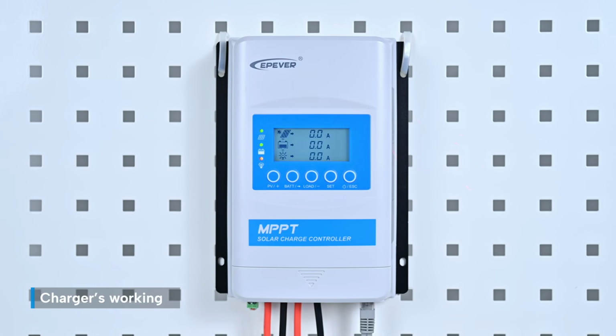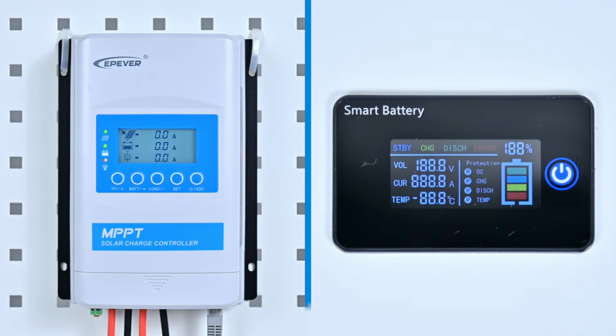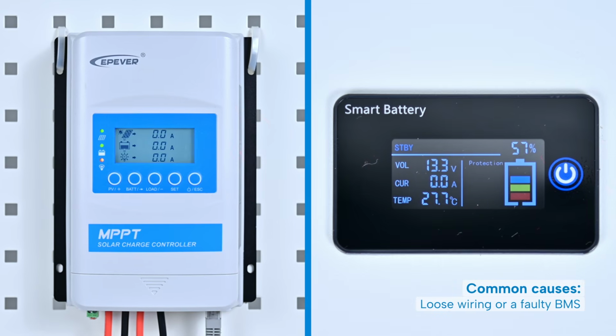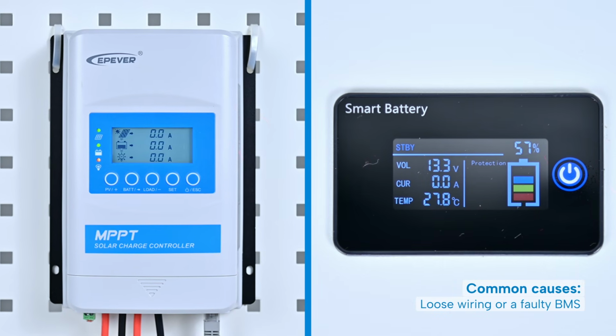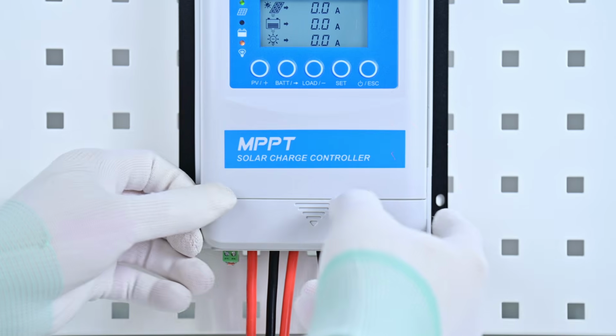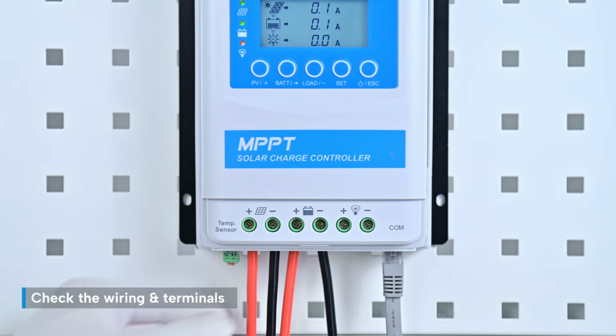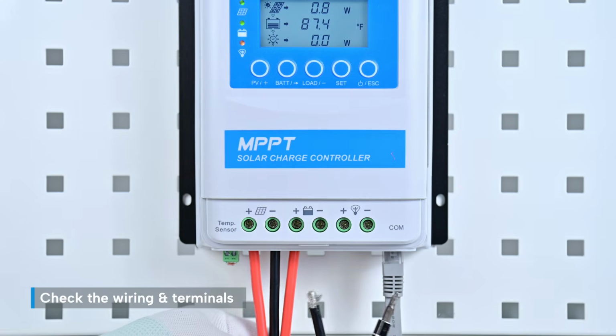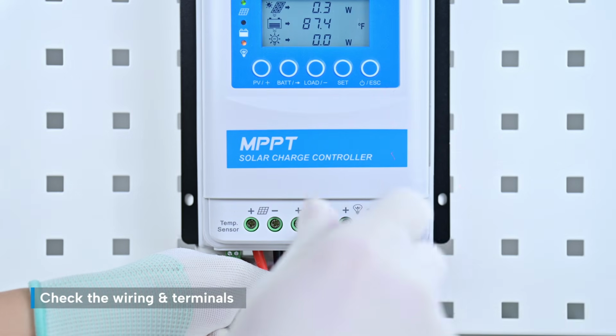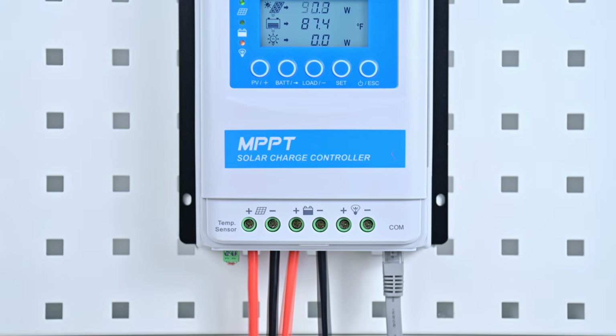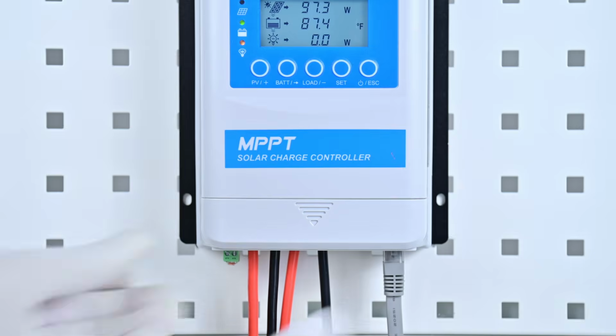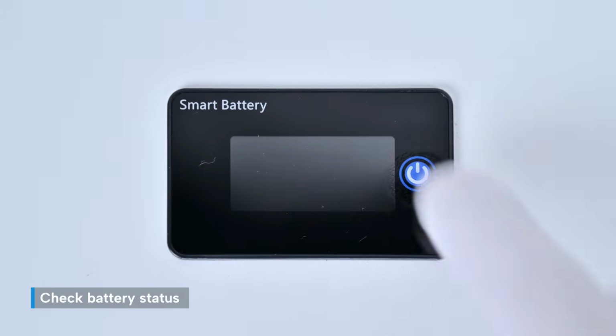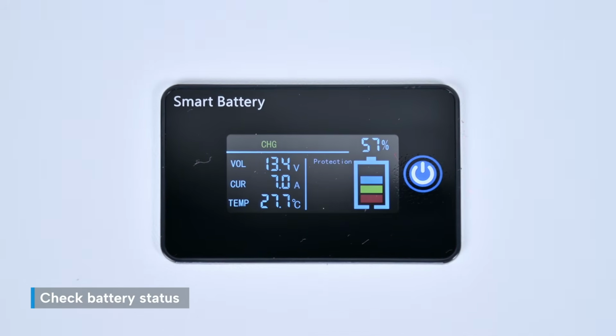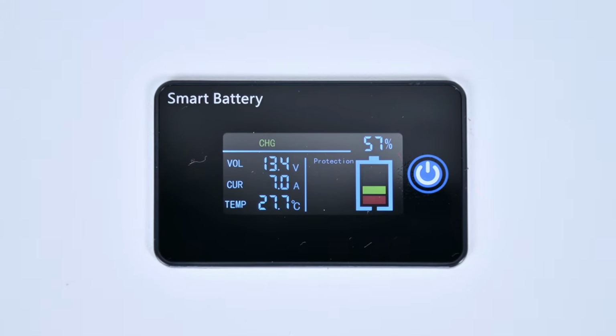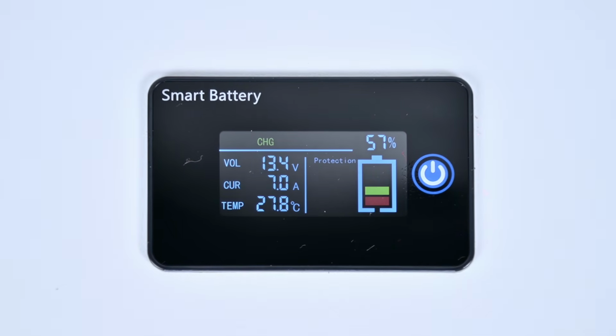You've got solar input, the charger's working, but the voltage won't go up. This might be caused by loose wiring or a faulty BMS in lithium packs. Check the wiring and terminals first. Under normal conditions, the battery should charge properly. If the issue continues, try disconnecting the battery or resetting the BMS.